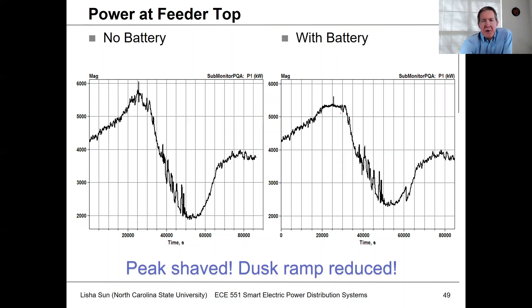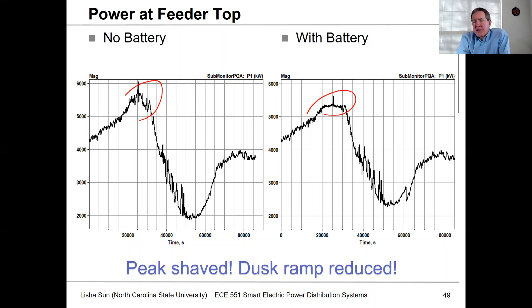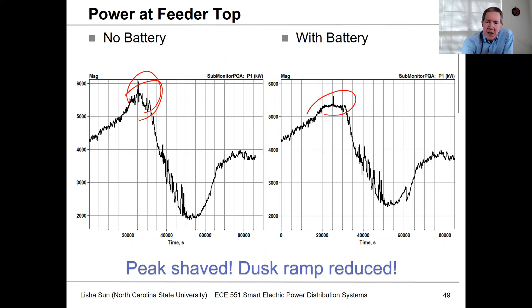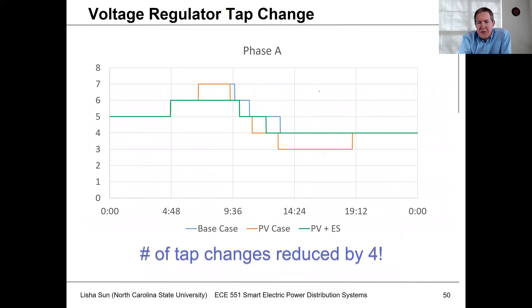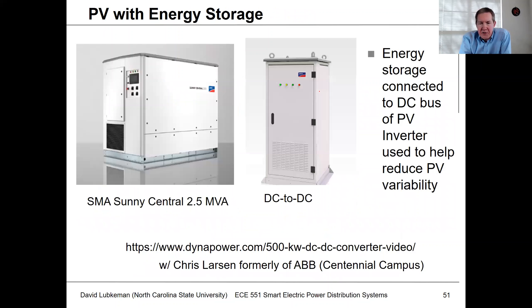This shows the power at the top of the feeder. When you're discharging into the system, mirroring the shape of the peak, you can level it down to a great extent — helping reduce the morning peak. This also has some positive impact on tap changes.